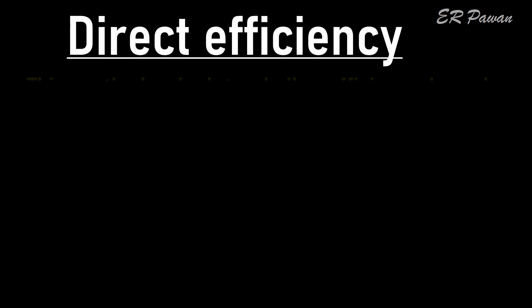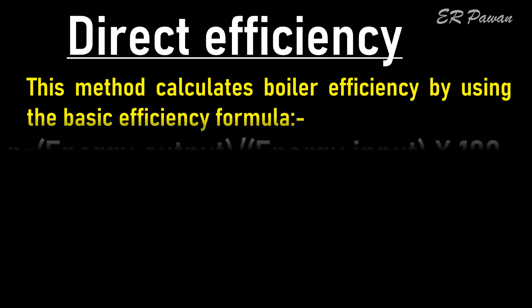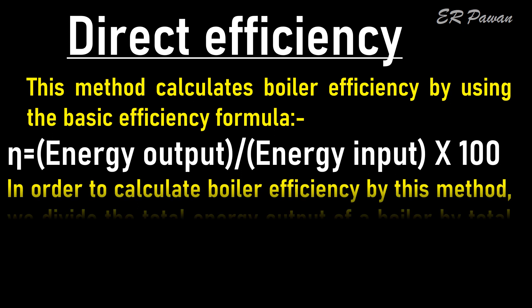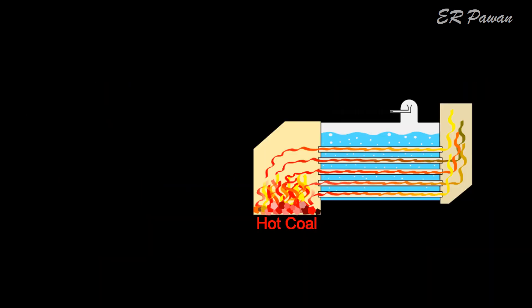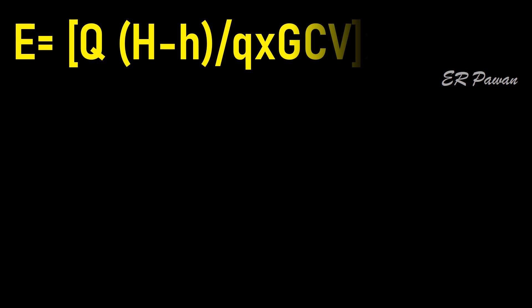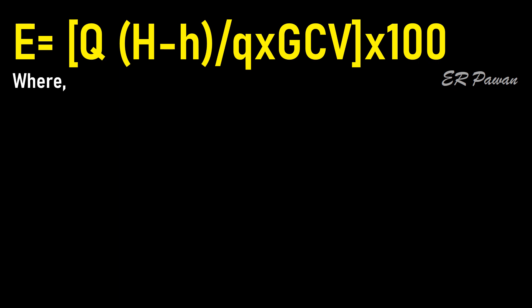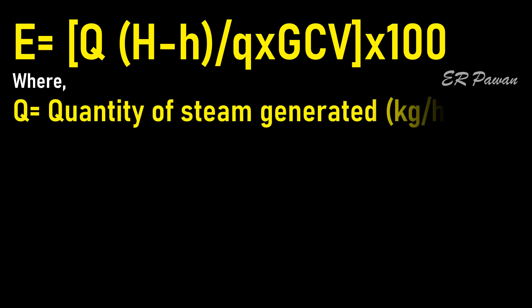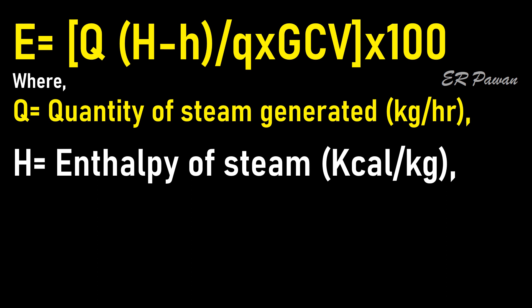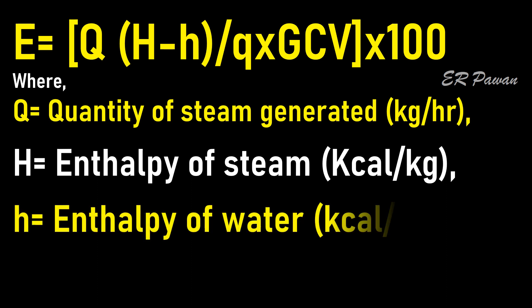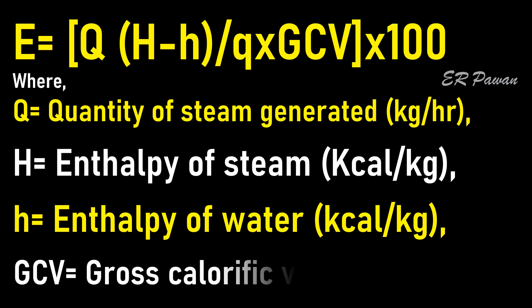Direct efficiency: This method calculates boiler efficiency by using the basic efficiency formula. We divide the total energy output of a boiler by total energy input given to the boiler, multiplied by 100. The formula is: E = Q × (H - h) / (q × GCV) × 100. Where Q equals quantity of steam generated in kg per hour, H equals enthalpy of steam in Kcal per kg, h equals enthalpy of feed water in Kcal per kg, and GCV equals gross calorific value of the fuel.